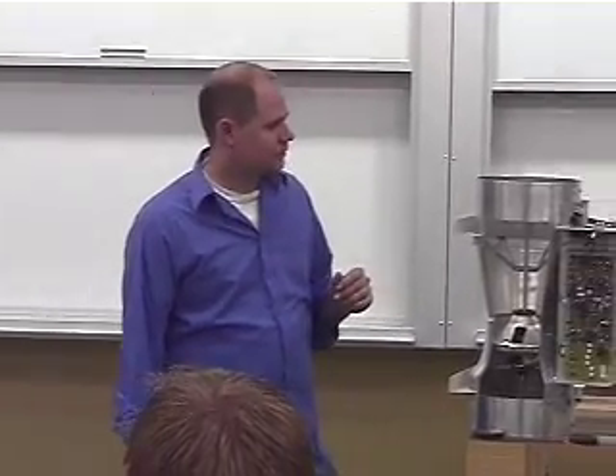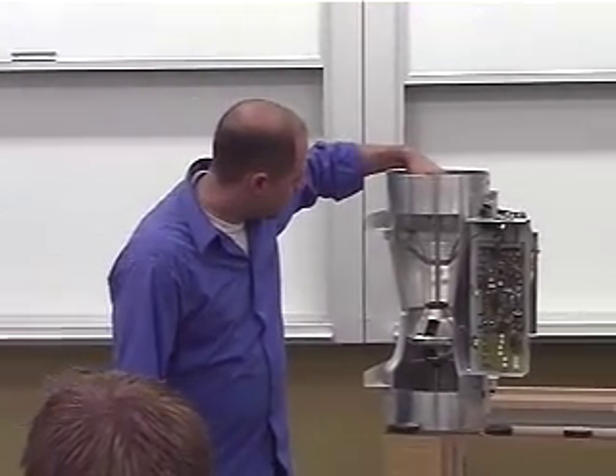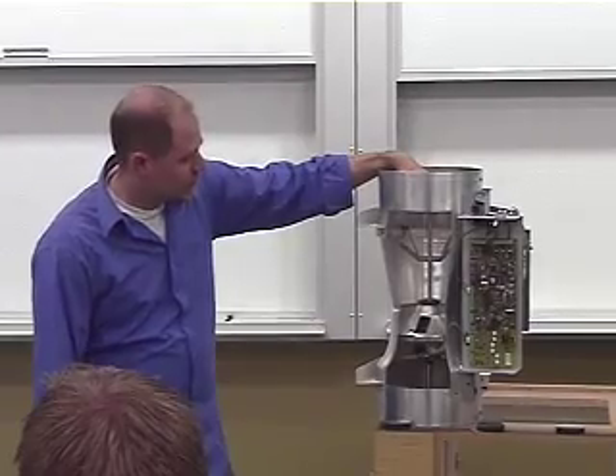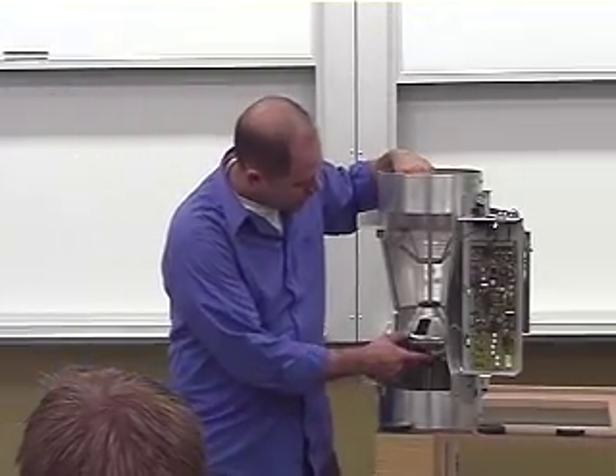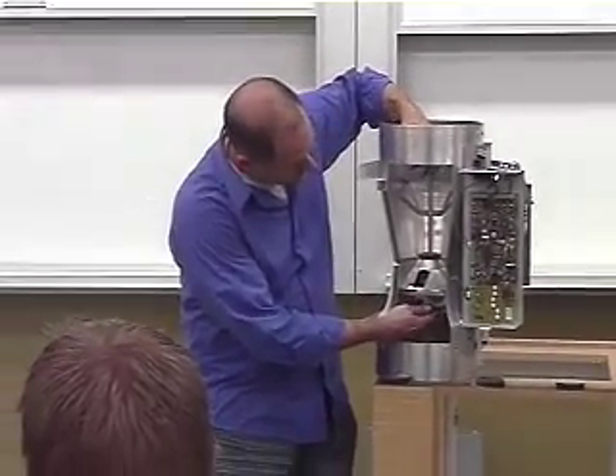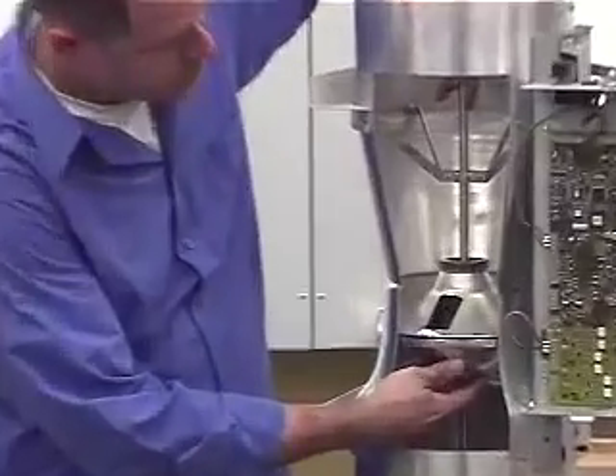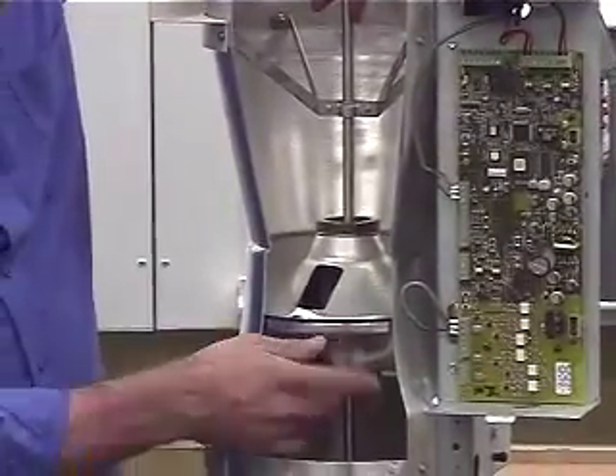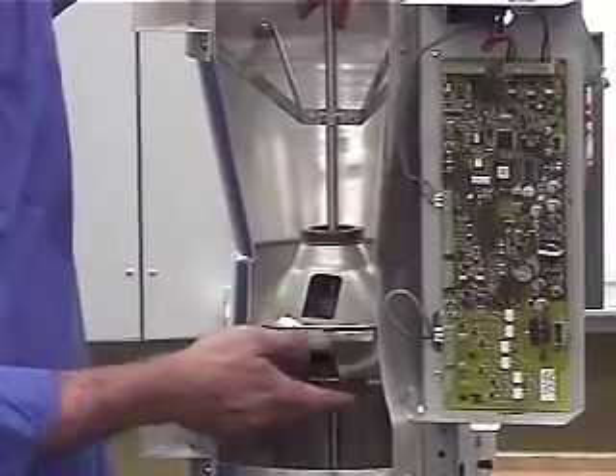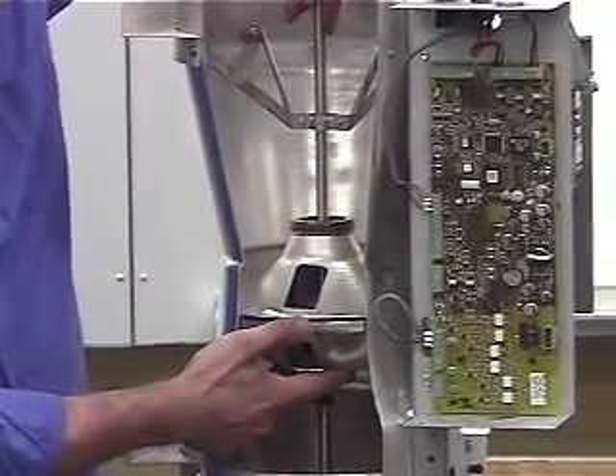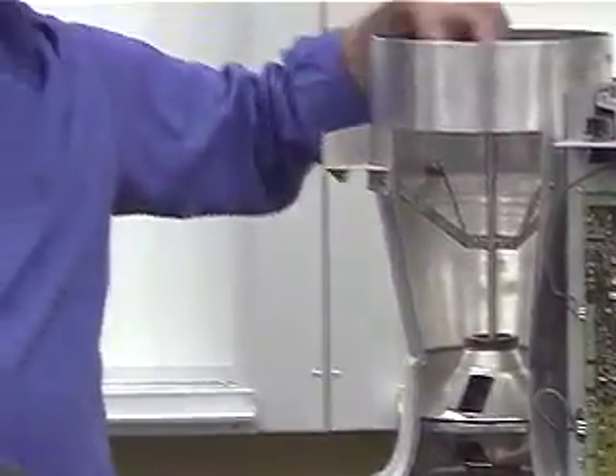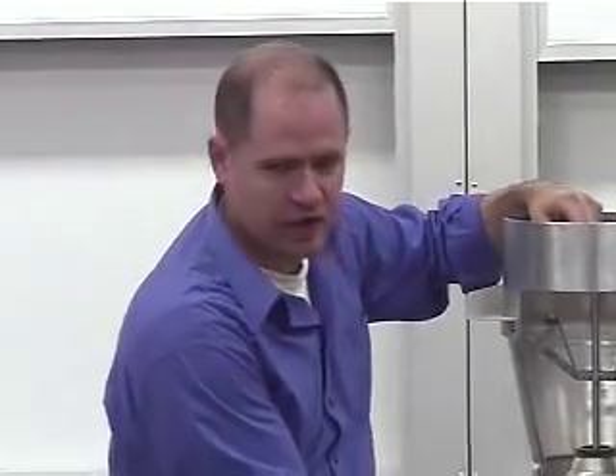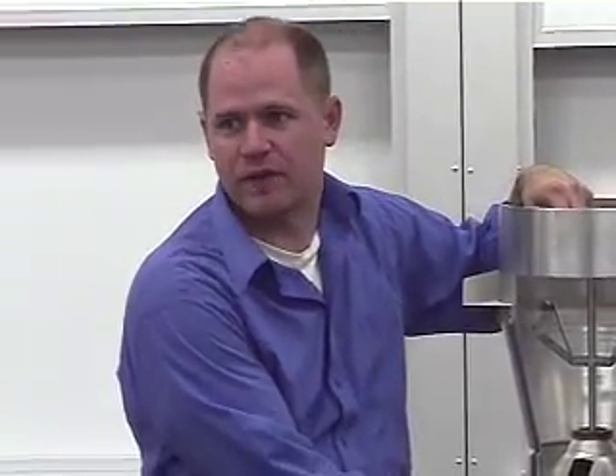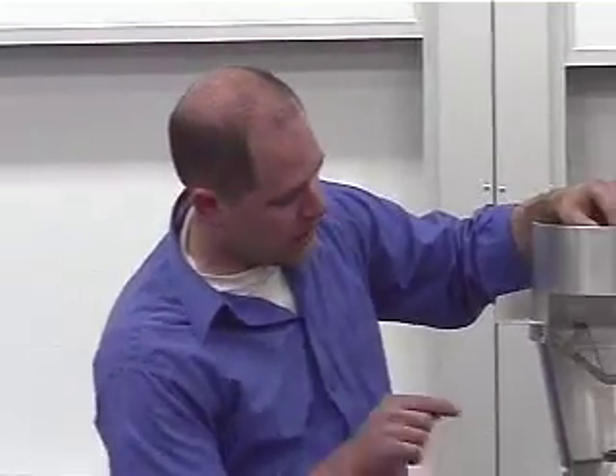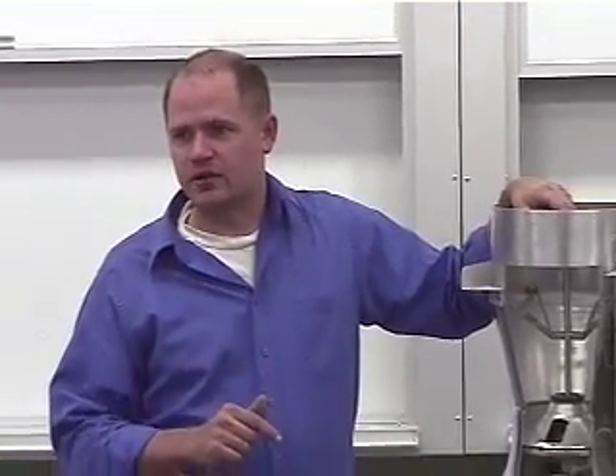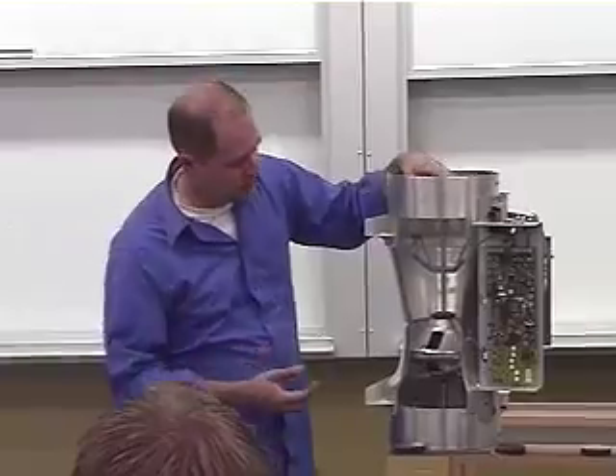So, let's see if I can remember where I was. Okay, so the cone can drive in and out, and like I said, this pressure, as long as it's right, will press down the spring just enough, because the spring is designed with a specific resistance in mind, so that no matter what the pressure is, as long as it's within the range on the upstream side of the cone, it'll hold just the perfect position. The airflow on these is critical. The direction is critical to be able to maintain that.